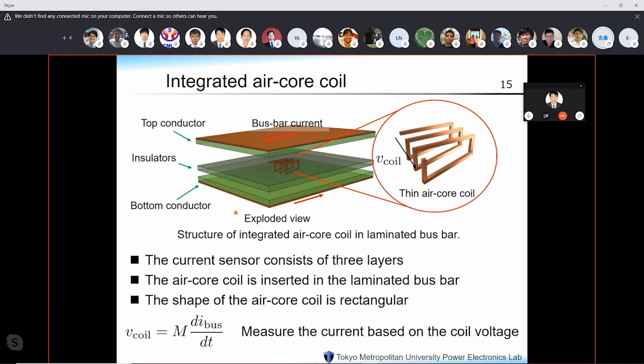This current sensor consists of three layers. The top and bottom layers are conductors, i.e. bus bars, and the middle layer is insulators. The thin air core coil is inserted in this middle layer, and the shape of the air core coil is rectangular.